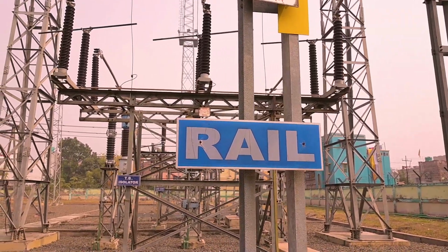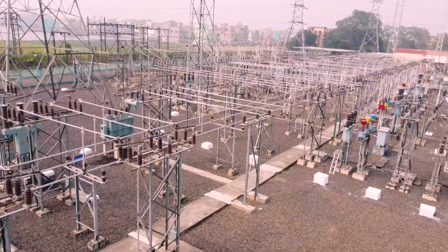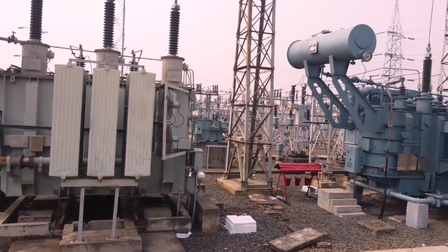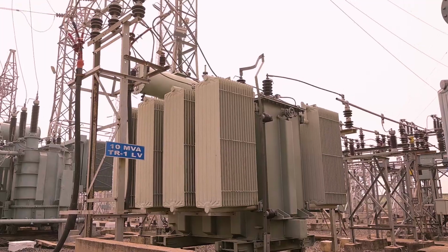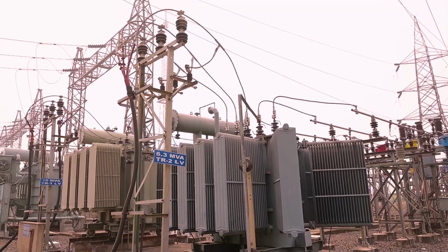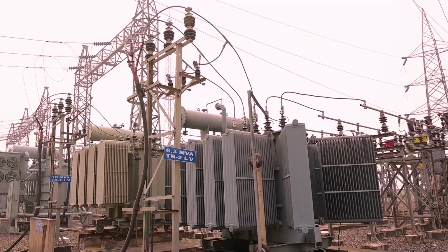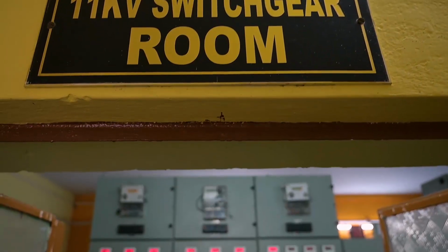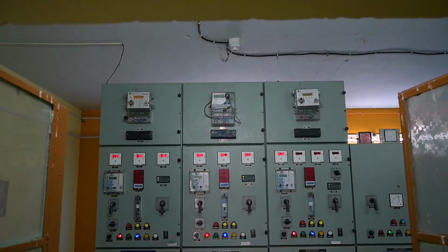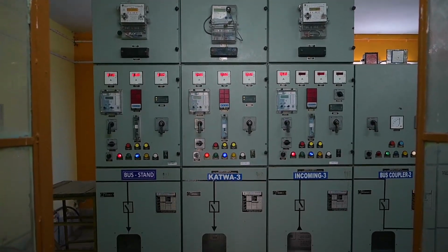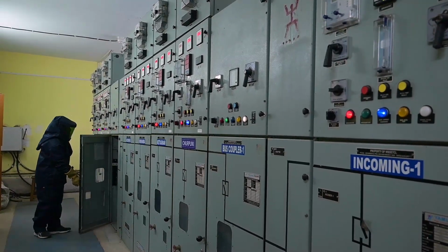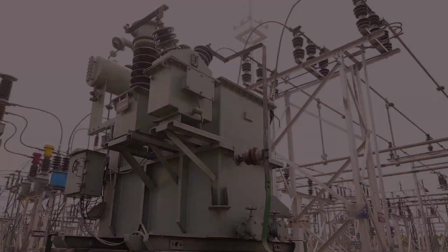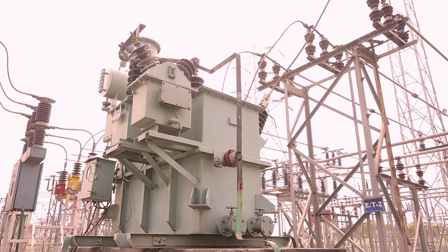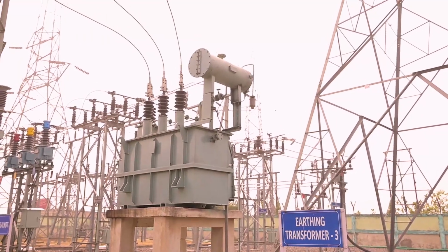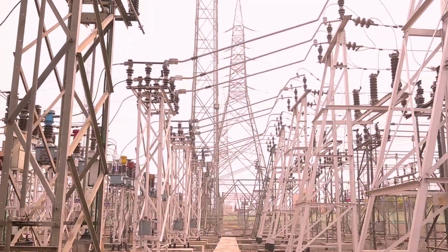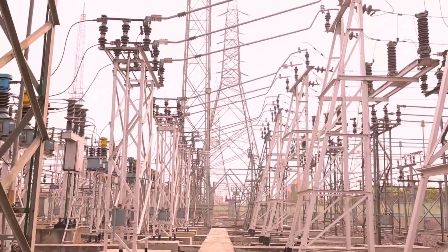There are three numbers of 132 by 33 kV transformers and three numbers of 33 by 11 kV transformers to feed power to the 33 kV and 11 kV system respectively, with a total capacity of 150 MVA. Three numbers of earthing transformers are installed in the system for protection of the delta connected 33 kV system, out of which the third one was installed recently.